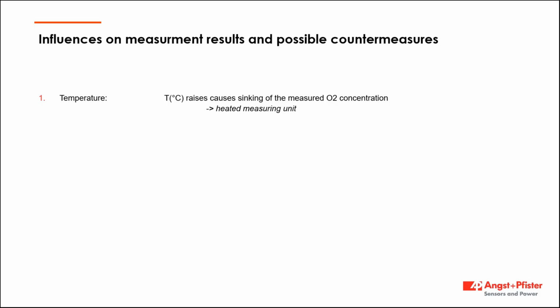So what you have is actually, if you have a rising temperature, you will have a lowering in the oxygen output. This can be solved as a countermeasure by having a heated measuring unit. That's what I said previously, that our oxygen sensor is temperatured at 55 degrees.